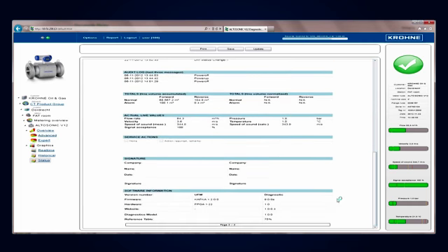One thing we put in here is a box where 2 people can sign. The idea behind this is a report is made monthly, and for example the service engineer and the supervisor sign off that this meter was okay. If there's ever discussions about the accuracy or about delivery of the gas, those reports might be a big help in saying no, this meter has been okay. One step further, but that's probably a little bit in the future, is with these reports you might be able to extend your recalibration dates, since you have proof that the meter is okay.